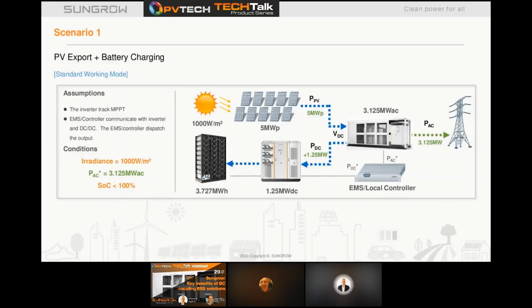Here we have the first of our scenarios. This would be considered a standard working mode. So this is PV export and battery charging. We can see here that we have full irradiance onto the array and it's producing 5 megawatts of yield. The PV inverter is in charge of the MPPT control and the priority is export. So you can see here that it's taking 3.125 megawatts out into the grid.